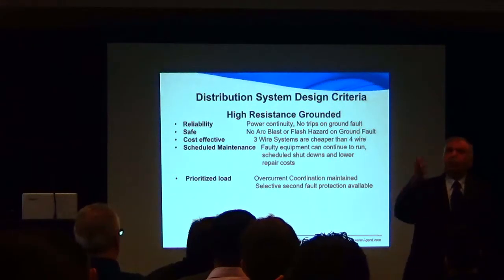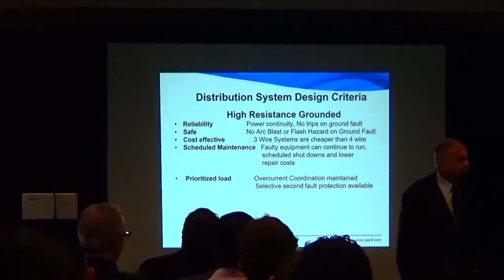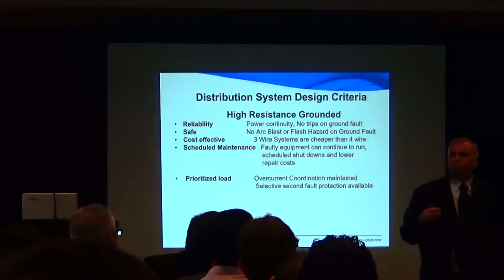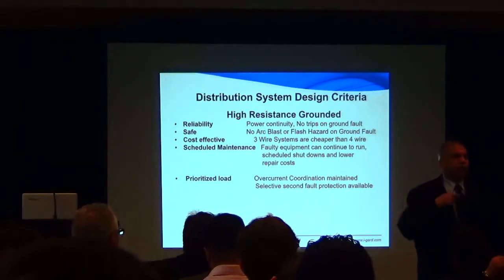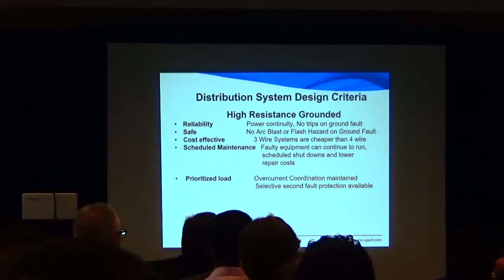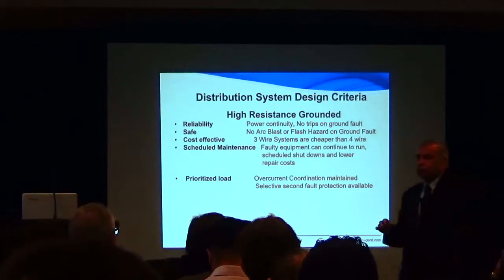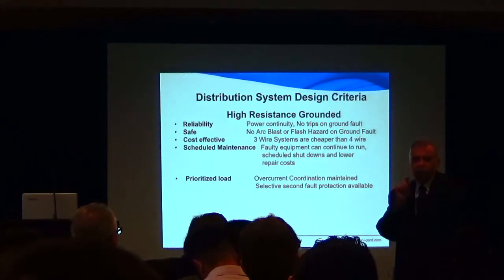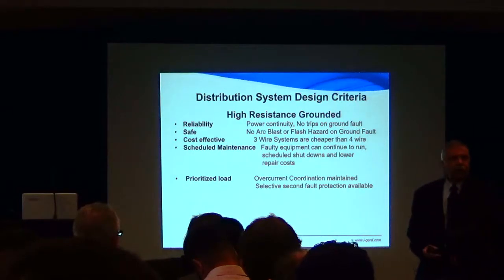In a distribution system like this plant, 600 volts, you will not know where the fault is if there was a fault. You will get an alarm, but then, make sure that you have in your specification this one additional element. It goes a long way to have satisfactory operation. Spell out how he is going to find it. Help him find it.